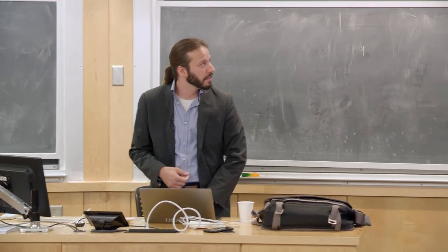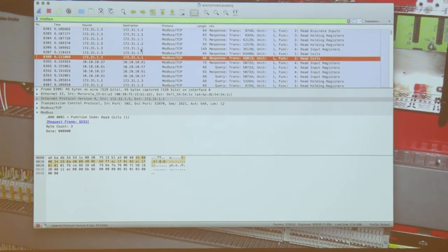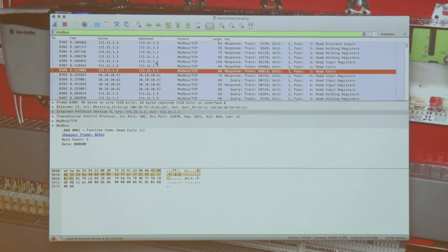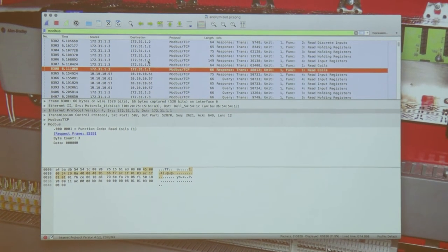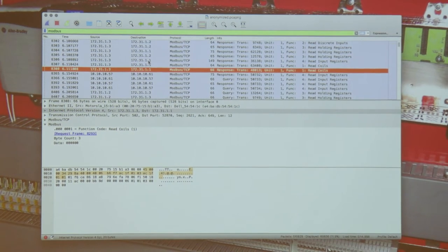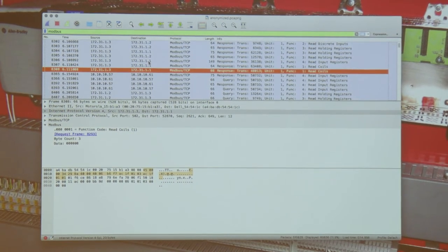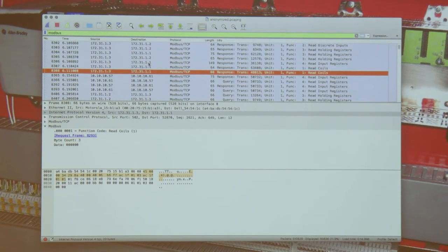This may be a bit difficult to read, but what we have is two machines, actually several machines talking. One of them, 172.31.1.1, is a master device that is querying another PLC, 172.31.1.3, highlighted there. It is very basic. It is giving a function one, which is a read coil. And then the client responds with a response back with the Boolean of that coil, zero or one.